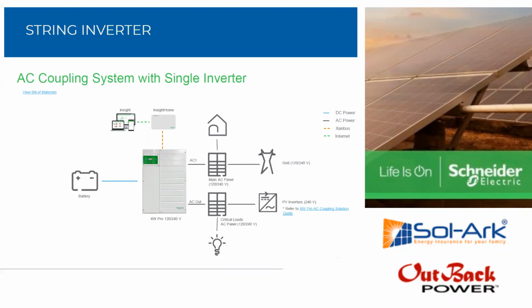when the battery is seeing that the home is drawing too much, it can alert the service panel to turn off those large 240 volt breakers. And this is really valuable because load shedding in the event of needing to preserve your battery is the number one thing you can do to prolong the life of your battery during an outage. So Enphase is doing designated breakers for any given 240 volt load. Generac also has this capability with their smart management modules today. Those are essentially the same, performing the same feature as Enphase's.